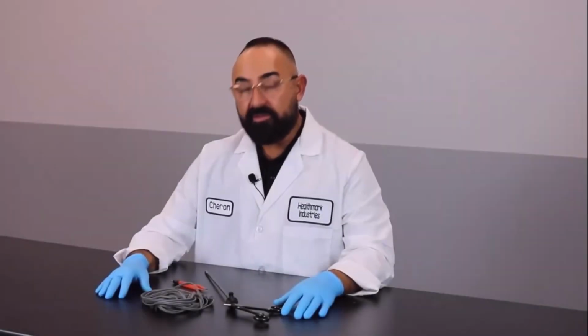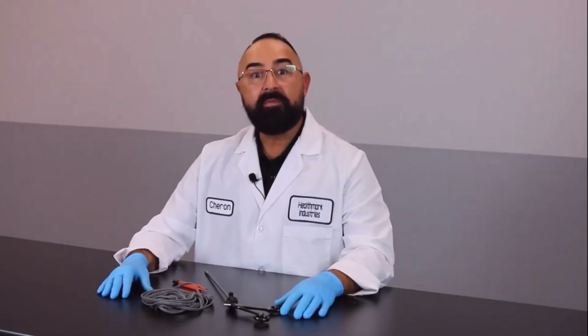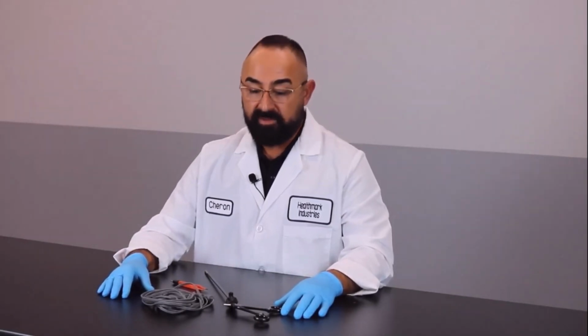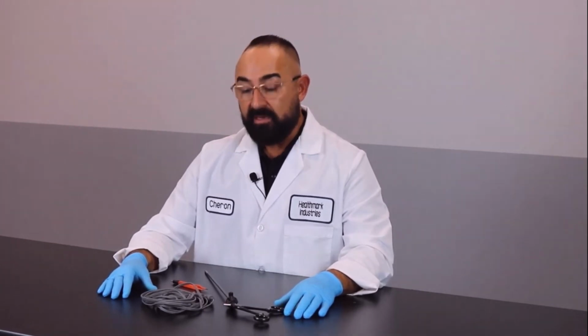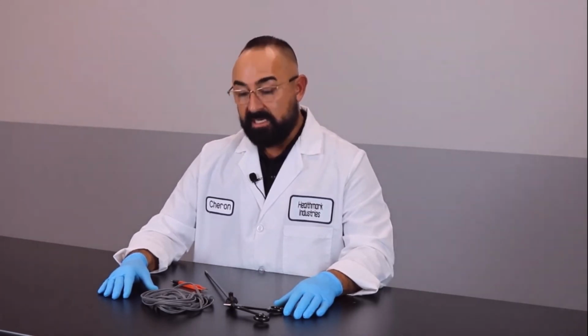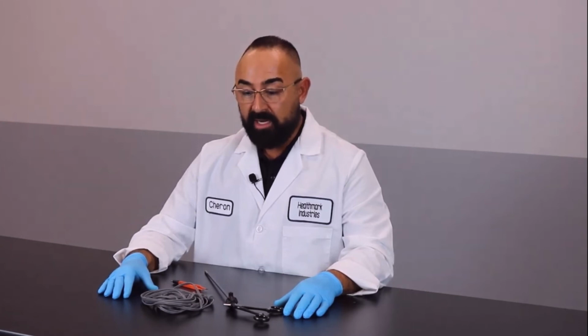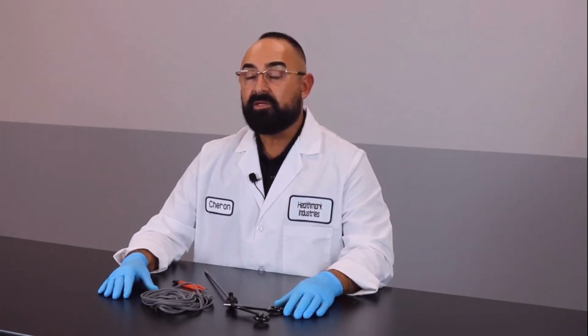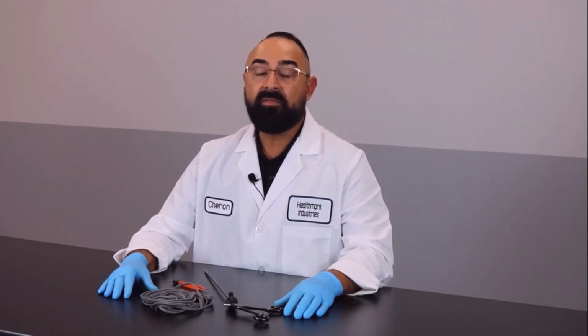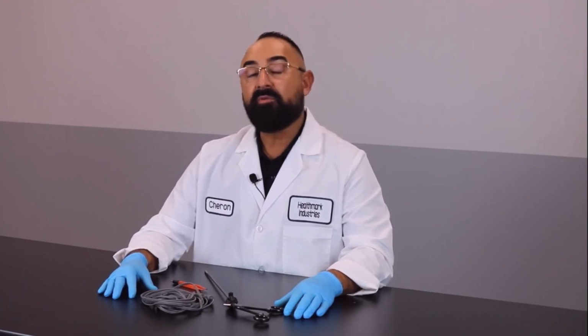As you saw in this demonstration, the instruments used were damaged, and it's very important that those damaged items are taken out of service. ANSI AAMI tells us that each of those insulated devices that are processed need to be tested every time. The McGan insulation tester did pick up numerous breaks, and these breaks can actually cause surgical burns in the patient internally and externally, OR fires, as well as burning through the glove of the surgeon. This is why it's really important for our patients to make sure that we're testing.